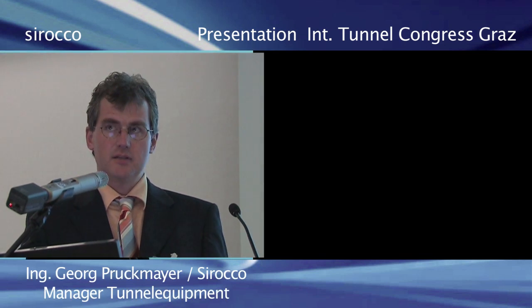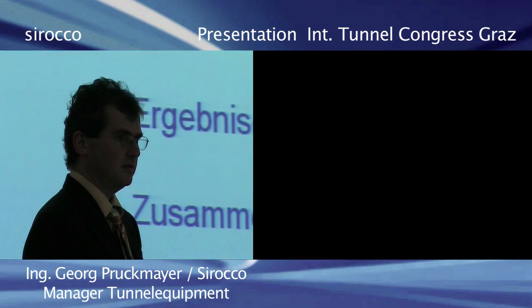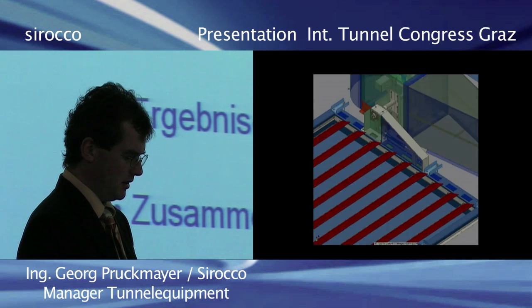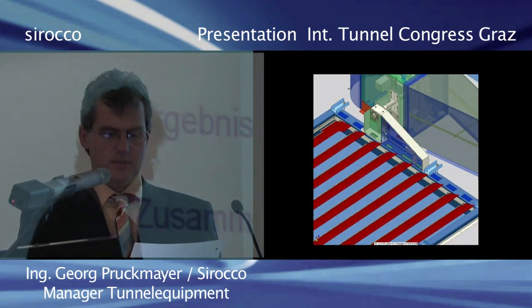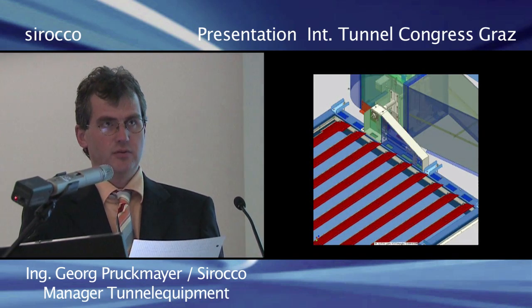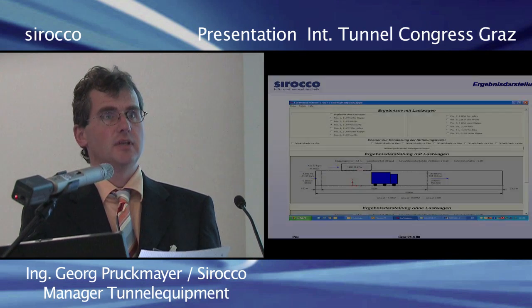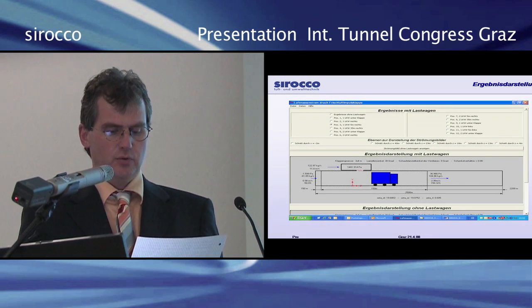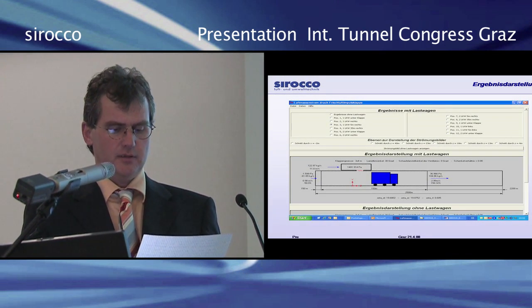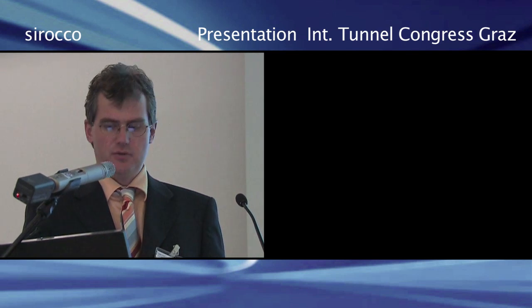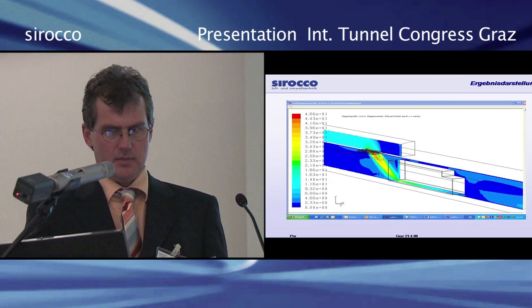The fresh air impulse valve is used in the tunnel ventilation system as a kind of nozzle. It blows fresh air into the tunnel and reduces the longitudinal speed in the tunnel, and in case of a fire, allows for selective extraction at the valve.